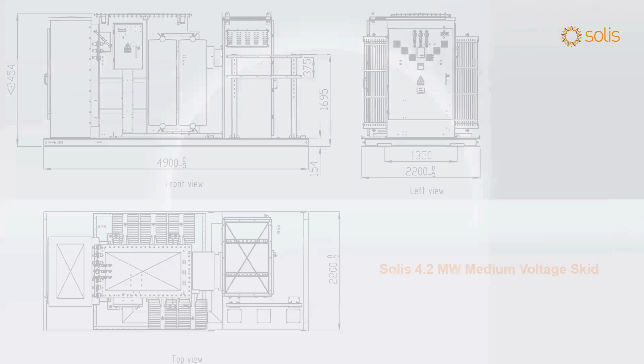This happens to be our 4.2 meg medium voltage skid, but we can set these up for 2.7 or 3.3 using the 125s or 185s. You don't necessarily need to wire it all for 800 volts at 250 using our 255s or 350 kilowatt inverters. You can use our 125s and 185s with that skid and combiners to set up a 600 volt central inverter solution. The objective here is to lower cost and increase margin for you guys.